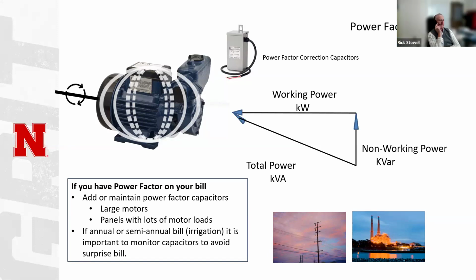I was just going to chime in that I'm seeing the same problem in a lot of our facilities, and it's on all types of energy consuming equipment, but specifically electricity. The solution has seemed to be variable speed, variable output motors and equipment. But the problem is that encourages people to go big, and they tend to oversize and then run it at a lower speed, and they're actually being dinged because the power factor is poor at those low speeds. If they go oversized, it's a double whammy—they're oversized and then running at poor efficiency.